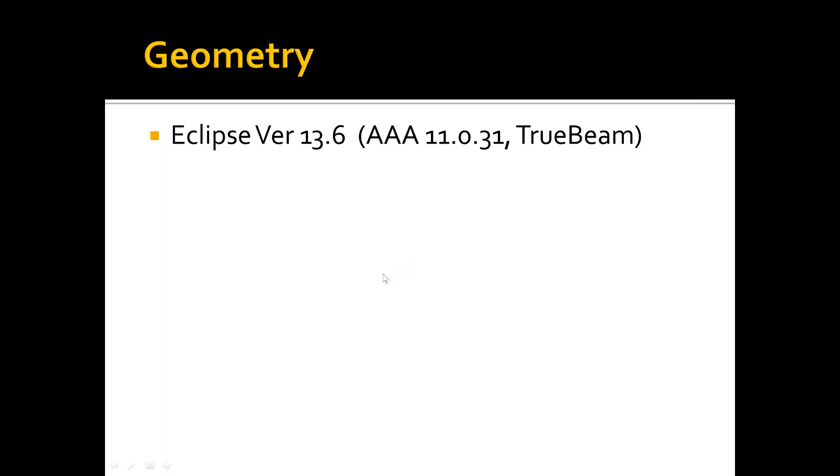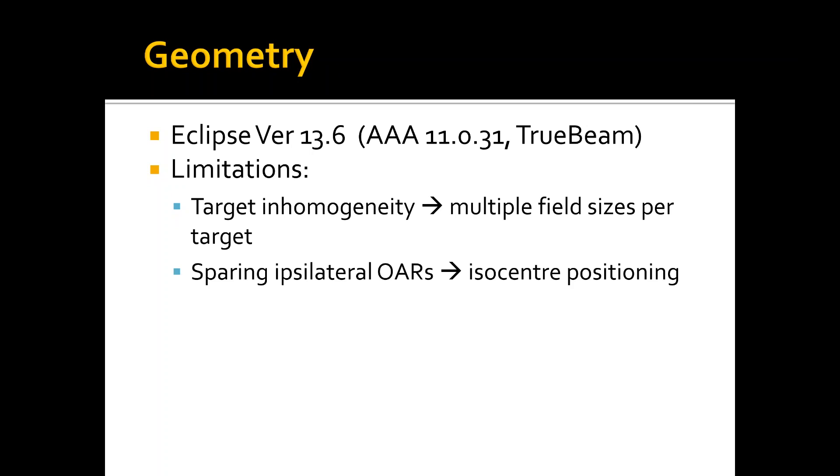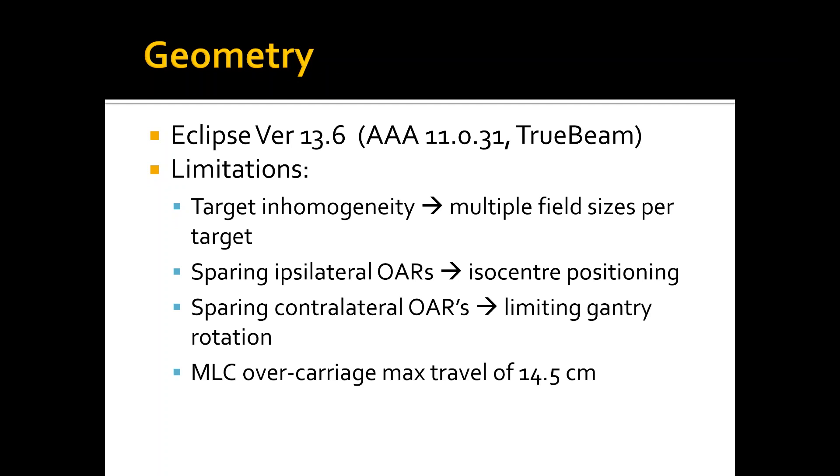My geometry comprises of Eclipse version 13.6 with AAA dose calculation algorithm together with the TrueBeam LINAC. Some limitations here. For target inhomogeneity, the fact that the target is comprised of supraclav, axilla, and left breast, this means that you have to use multiple field sizes per target. To spare the ipsilateral organ at risk, you have to be careful of your isocenter positioning. To spare the contralateral organ at risk, you have to limit gantry rotation. And we have this limitation of MLC overtravel maximum level of 14.5 cm, which gives you some limitation on your X field opening.